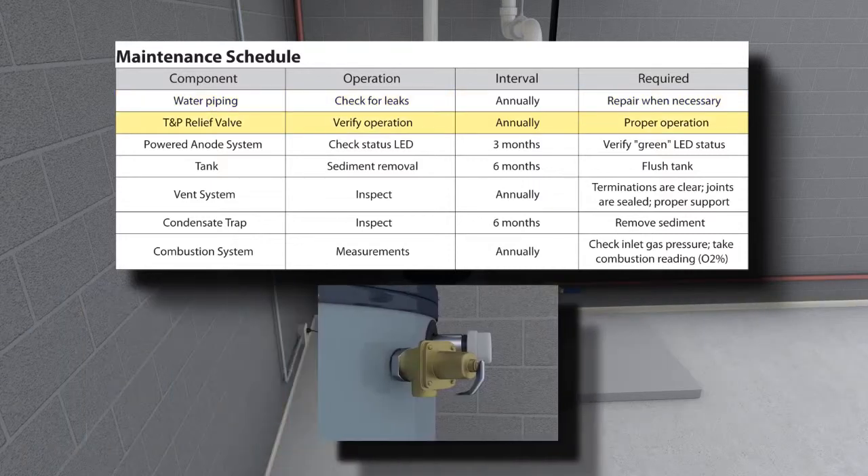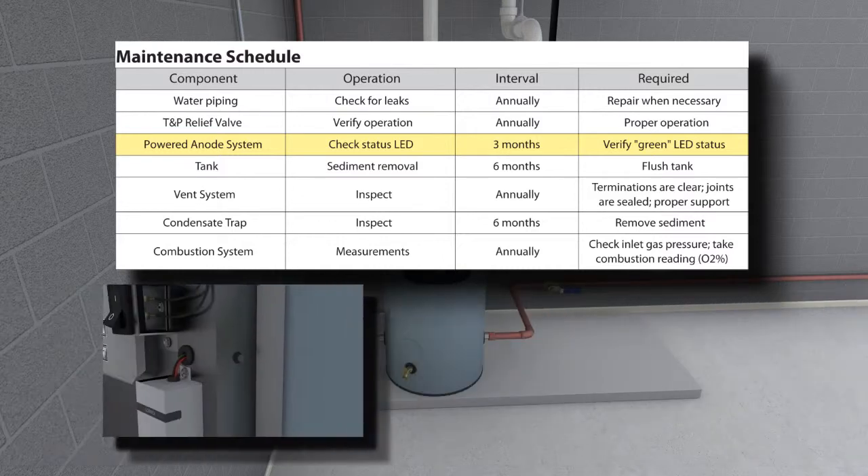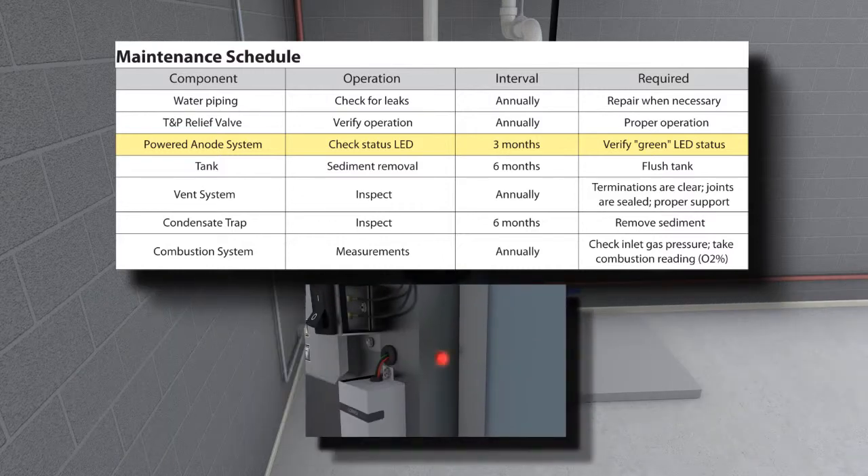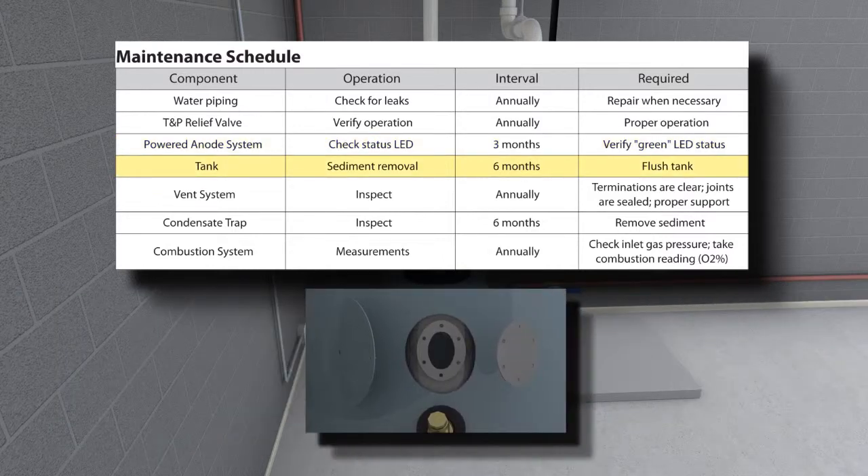The T&P valve function should be checked every year. The cathodic protection system module and status LED are mounted on the control panel under the cover. The status LED will be green if the system is functioning properly, and will flash red if there is a system error.